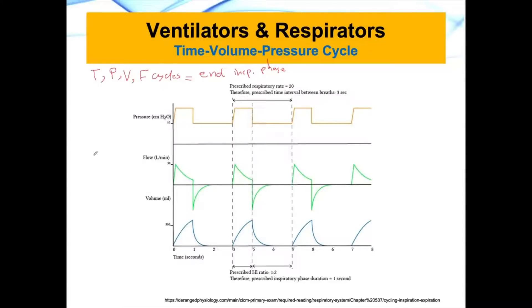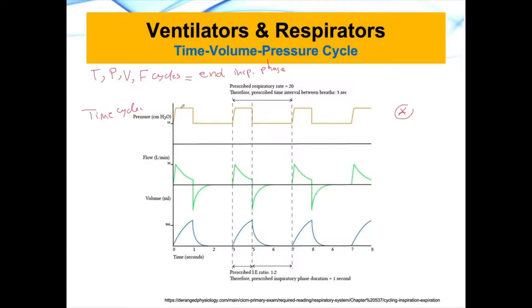An example of a time cycle is this one. A time cycle ventilator will behave similar to the top part of the schematic. What happens here is that we have pressure and we are asking the ventilator to raise the pressure from a baseline to a specific pressure and hold it for a certain period of time, push it inside the patient's lung, and then stop after a certain period of time to allow the patient to exhale, and repeat the same thing again.